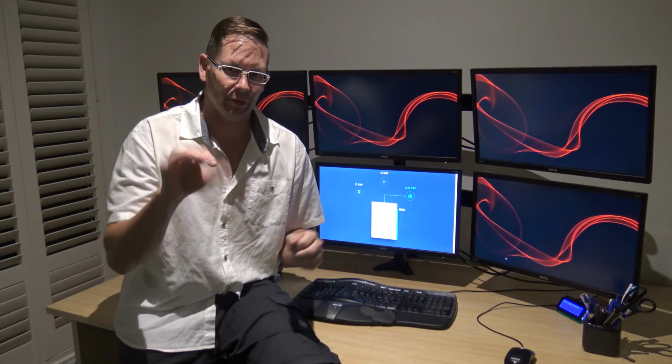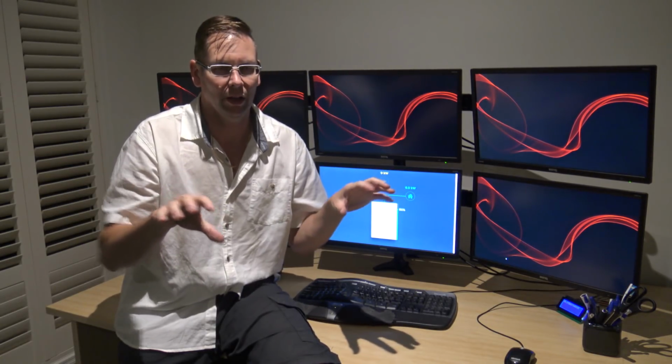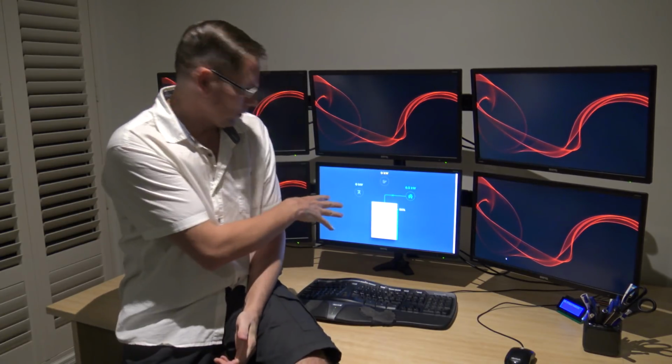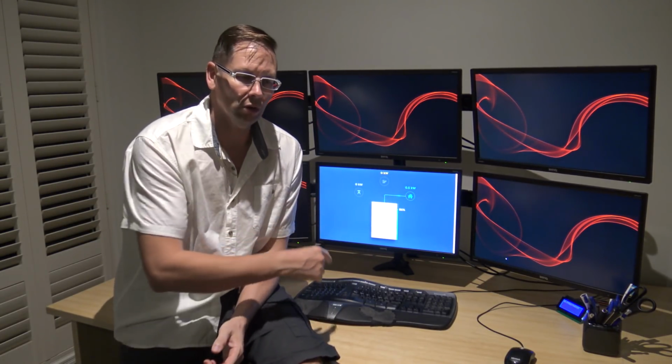And the third thing is the uptime of the actual Powerwall had reset. So there's two uptimes. There's the uptime of the gateway and the uptime of the Powerwall. And when this reboot happens, they both reset. Now, like on the interface here, if I manually stop the Powerwall and start it again, the computer aspect in the gateway, that's still up and running. But the uptime on the Powerwall will reset. But when it reboots, the computer's rebooting and the Powerwall, not just one or the other.